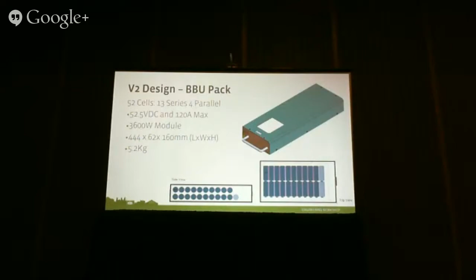Recall each cell is 30 amps, and with 4 in parallel, that's 120 amps max out of the BBU - each module is 3,600 watts. That's 300 more than the power supply, because of the efficiency losses when taking power out of the battery through the power supply to the motherboard. Each module is 5.2 kilograms, so weight-wise, huge win. That's roughly how it's arranged inside the BBU - there are 2 levels of cells, stacked on top of each other and next to each other.